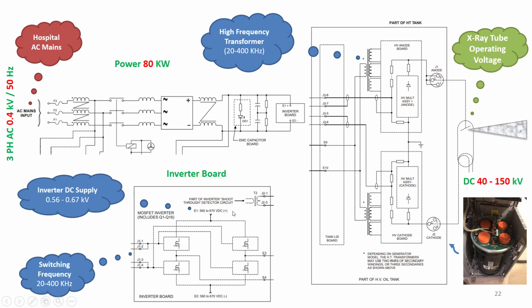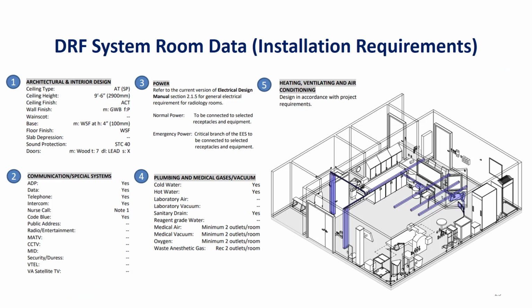It's supplied with 560 volt from the capacitors. The SPI company usually uses oil to isolate the air in order to avoid the arcing problem. Another also well-known and famous manufacturer of X-ray generators is the Spellman American company, which uses resonant inverting board technology and also uses boards to isolate air and avoid the problem of arcing.